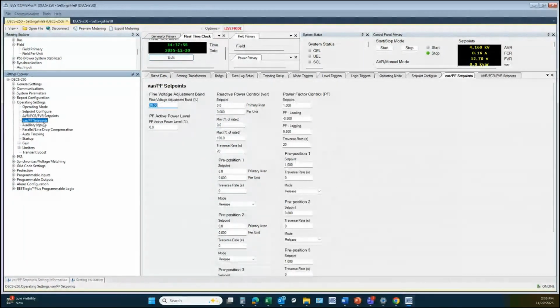So we continue, we go to VAR power factor set point. When your generator is online, tied to the utility grid, you may choose to run in VAR or power factor control. And as such, this is where you would set it up. Fine voltage adjustment band: if your voltage actually goes outside of that band based upon the rated voltage, then it will take you automatically out of VAR or power factor control and drop you back into AVR droop. Sometimes if you have a fault out on the line and your line voltage, your utility voltage, actually drops, you may want to come out of VAR or power factor control while that fault has occurred.